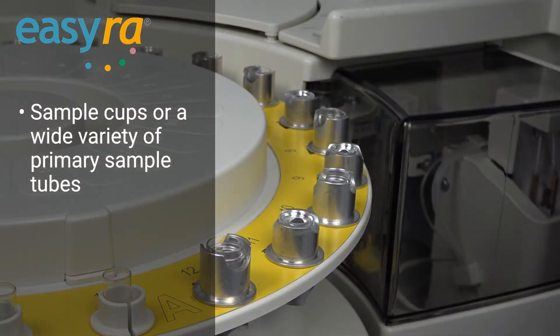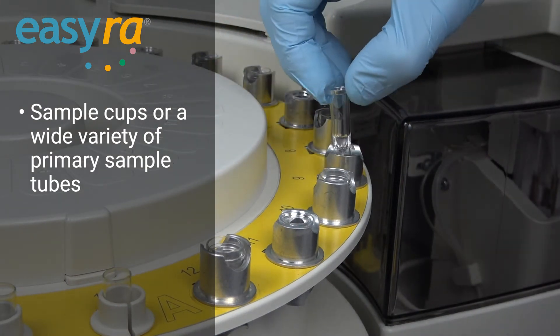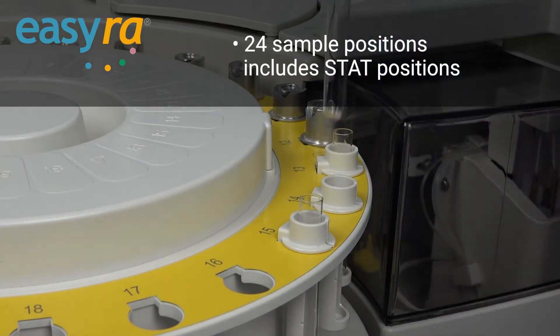Utilizing a variety of sample types and sample tubes, the easyRA allows for positive sample identification through positional IDs or the use of a barcode. The sample is placed in a 24-position sample wheel, including stat positions.